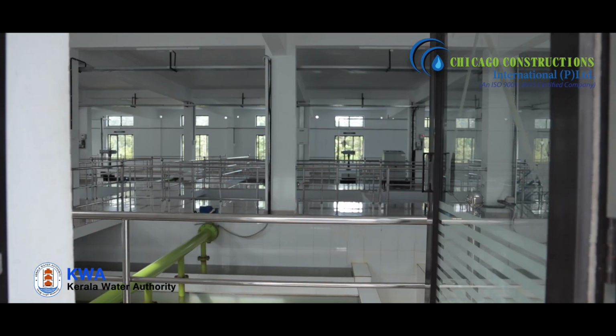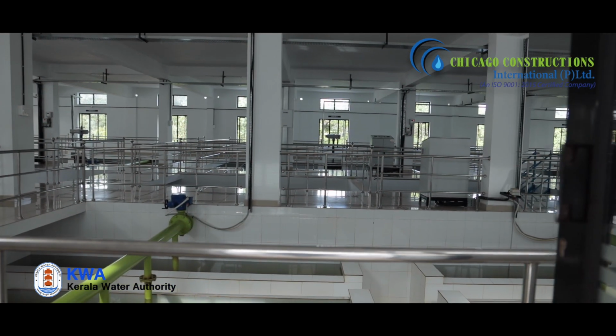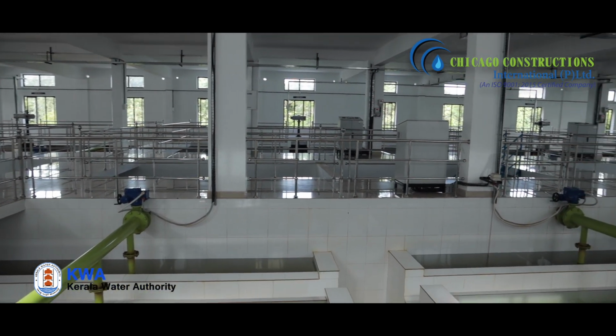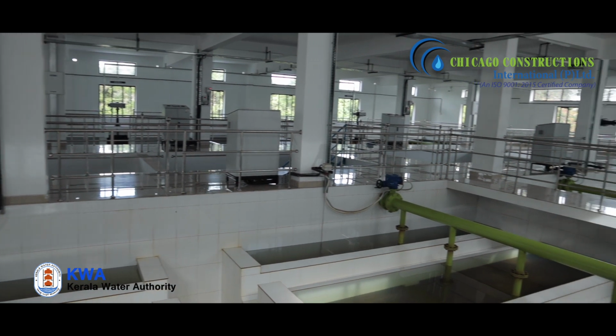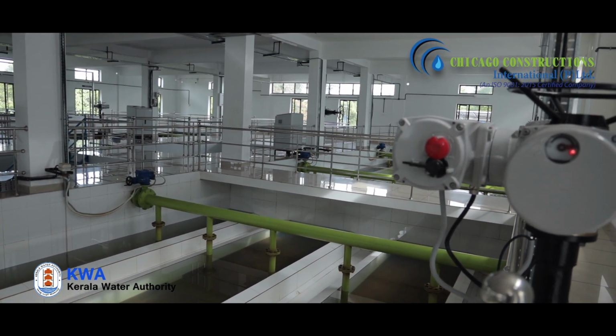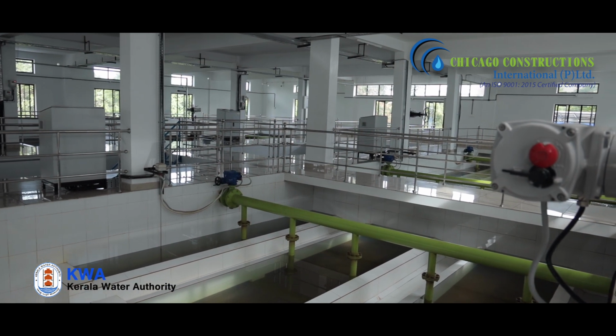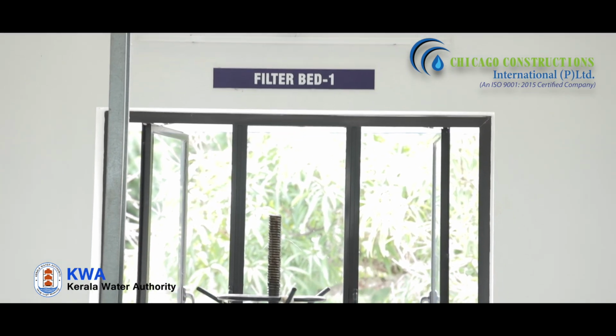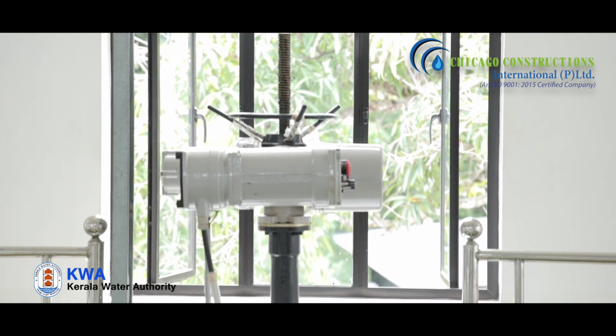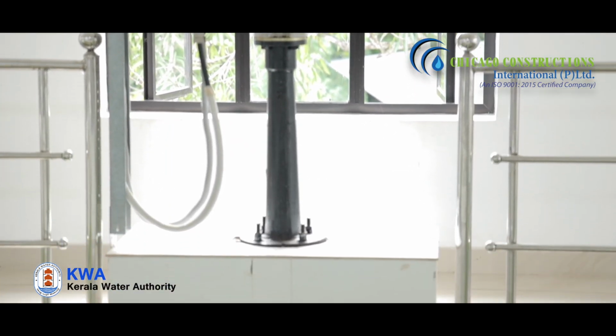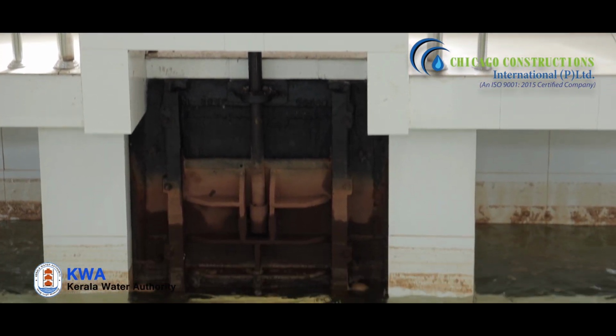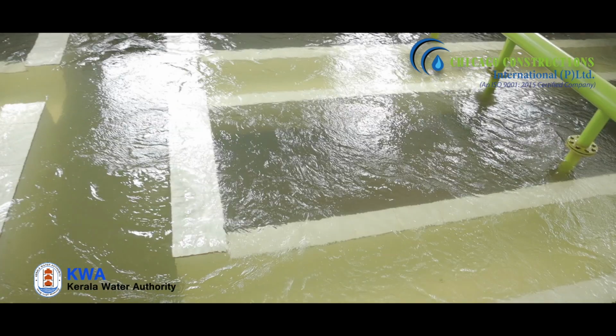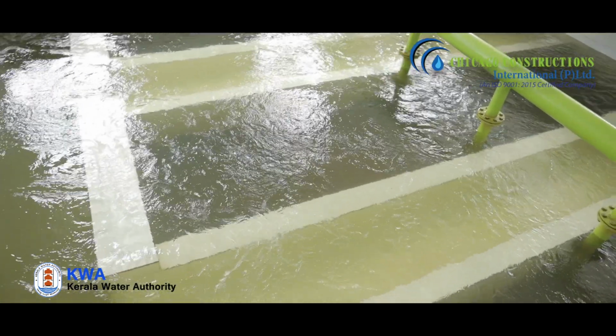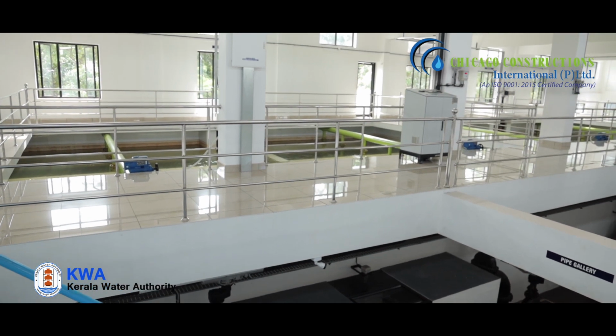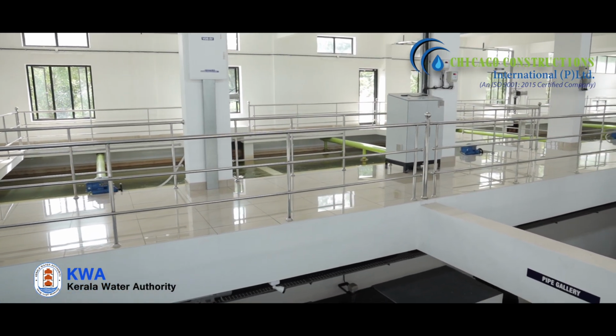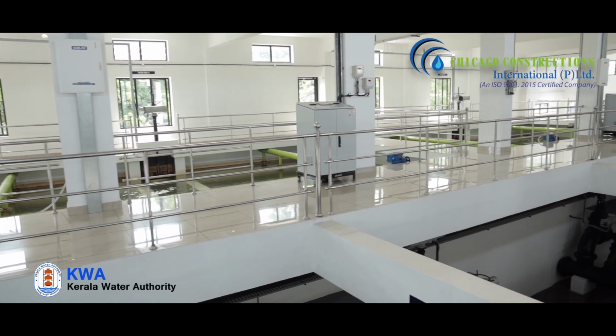There are 2 filter houses in the plant with a total of 24 filter beds, each bed measuring 5.2 x 6.6 x 2.7 meters. Rapid sand filtration is the method used in these filter beds, and it is a purely physical treatment process. As the water flows through several layers of coarse-grained sand and gravel, relatively large particles are held back safely. Each bed has 56 perforated PVC lateral pipes, each with a length of 5.2 meter and a diameter of 90 millimeter for clear water collection.